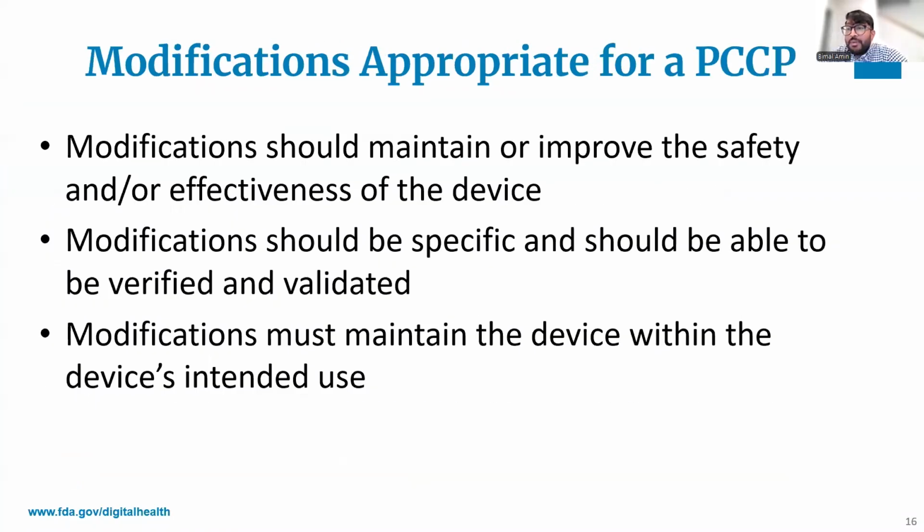So to recap, the proposed modifications appropriate for a PCCP must maintain or improve safety and effectiveness. They must be specific enough to be verified and validated. And critically, they must keep the device within its intended use and must allow the device to remain substantially equivalent to the predicate device.